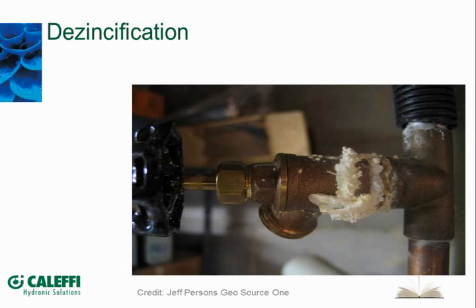We have situations where a lot of our brass valves and materials are now coming from overseas sources, and perhaps they're recycled and may have a higher zinc content than pure copper from years ago. It's something we want to watch out for. I watch refrigerant coils and question why we see so many leaks in refrigerant coils of recent, and I have to question if it might be within the chemical makeup of that copper, if there might be some residual zinc there. Those are yet to be answered, we'll put it that way.